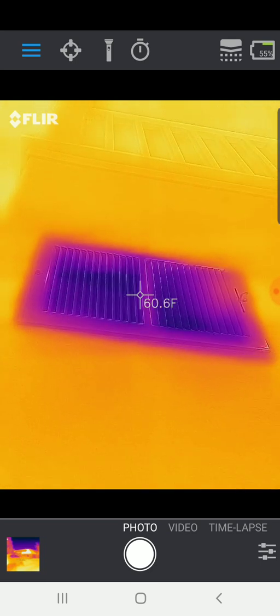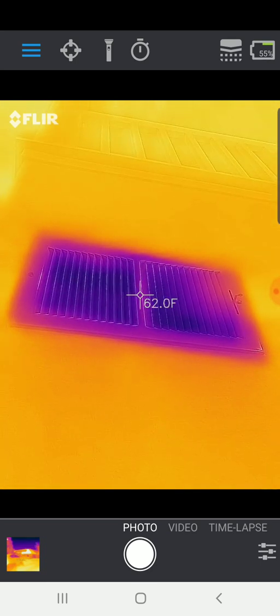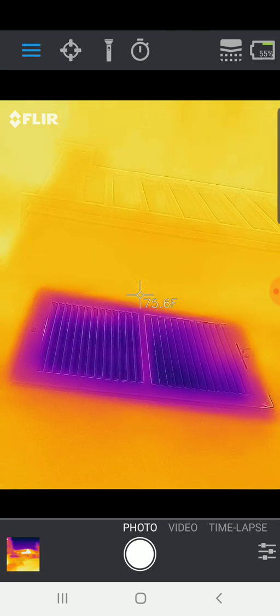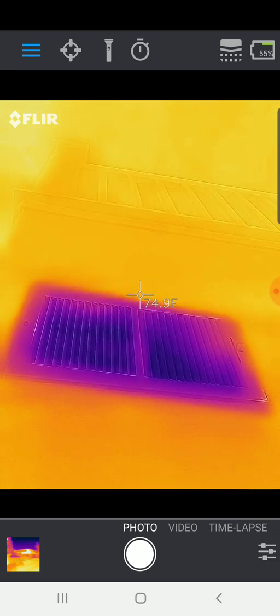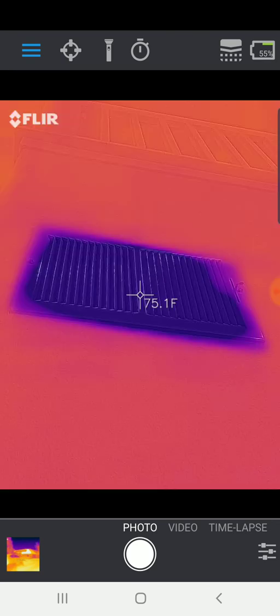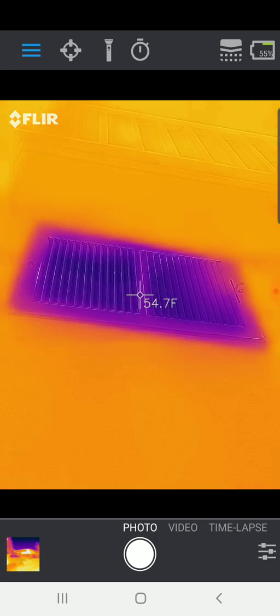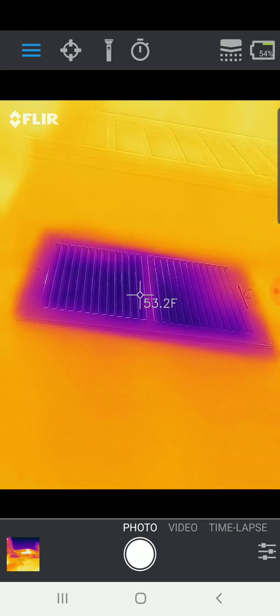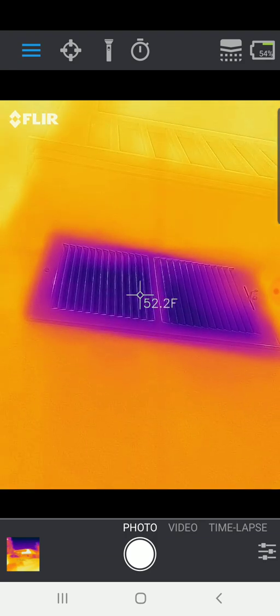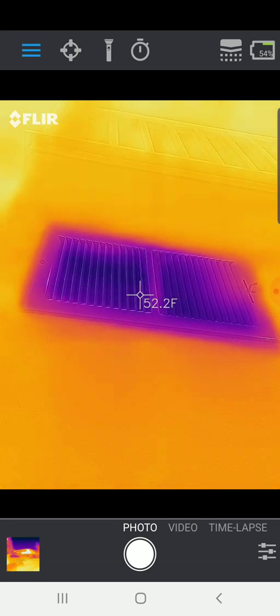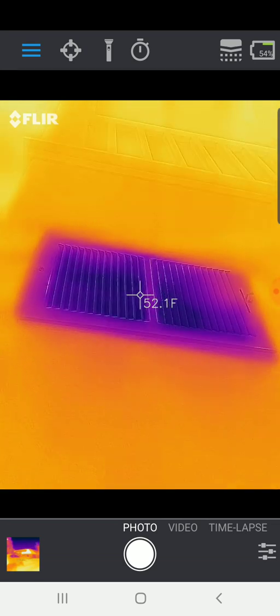And you can see in contrast to the fan where the air coming out is actually a little bit warmer, the air here is dramatically colder than the air around it. So if I look at the temperature of the wall, it's like 76 degrees up here. And then if I look at the register, it's 54, 55, 53.